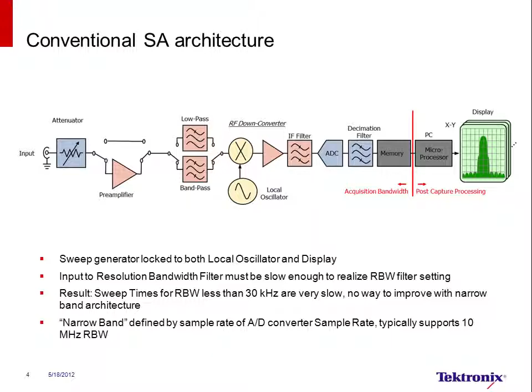Even if the analyzer in question has capabilities to use a wider IF up to 40 megahertz, these instruments still perform spectrum measurements using a narrow bandwidth signal path of less than 10 megahertz. Additionally, most all these instruments' RF specifications like image rejection and harmonics only apply when the instrument is used in the narrowband sense. Using a narrow RBW is essential to perform these low-level noise floor measurements to get the performance needed, but at the expense of slowing down the sweep speed dramatically.